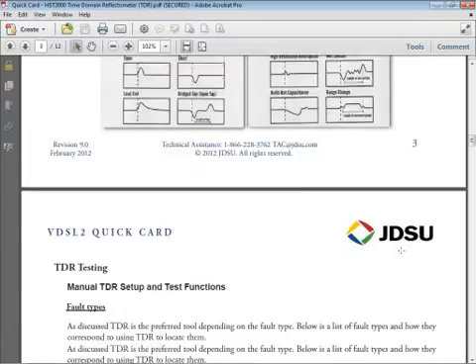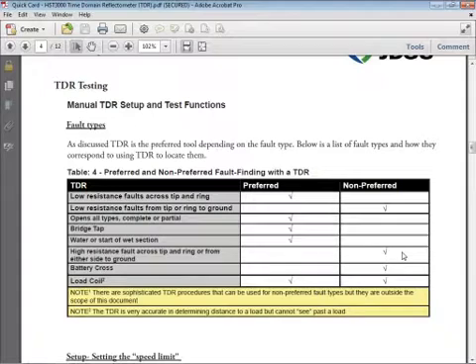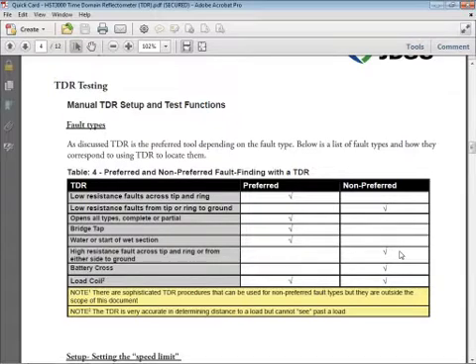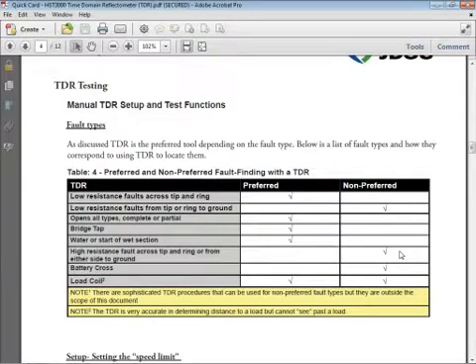Any good TDR instruction starts off with a discussion about what they're good at and what they're not so good at. What you're looking at here is a table that reflects common faults on the left, and whether or not the TDR is the preferred or non-preferred method for dealing with those faults. Low resistance faults across tip and ring — i.e., shorts. TDR is pretty good at those if they're low resistance. They've got to be hard shorts, solid shorts, whatever terminology you use. It's got to be a pretty solid short for the TDR to see it.